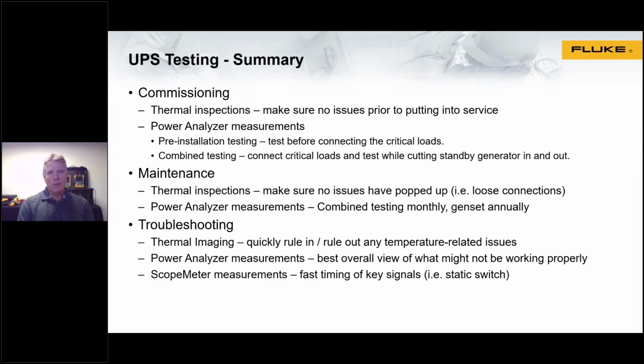Power analyzers are very useful in both pre-installation testing with load banks and then combined testing once you connect your critical loads, and then while cutting the standby generator in and out. And then on an ongoing basis, thermal inspections are always a great screening tool. Power analyzers can be used on monthly and or quarterly testing, and then also by involving the genset annually. And then also all three types of tools would be very useful from a troubleshooting standpoint.